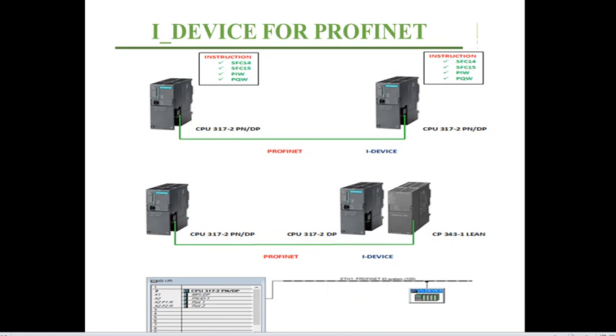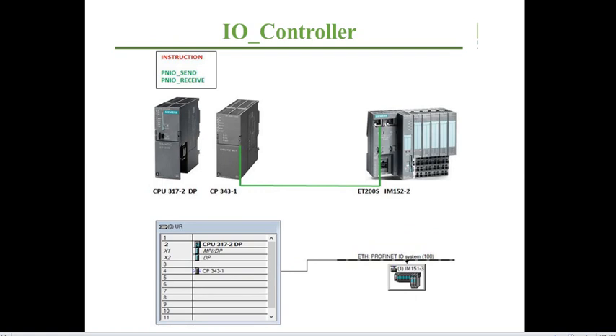The last type is PLC to IO module — not PLC to PLC. The PLC only has a MPI port and no Profinet port, so we use a communication processor module. The ET200S IO module has only a Profinet port, so the communication processor connects them, allowing the IO module and PLC to communicate. The instructions used are PNIO_SEND and PNIO_RECV.